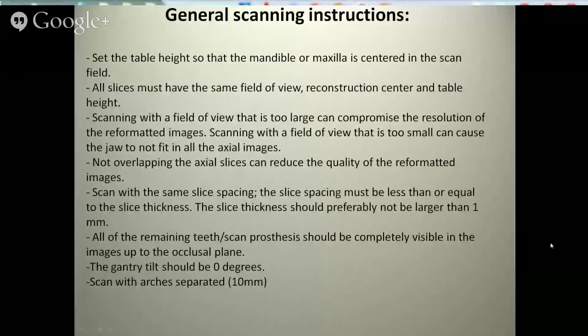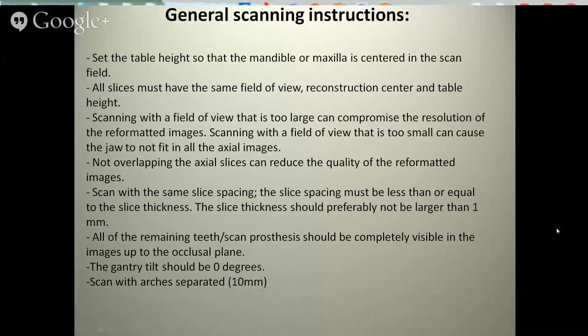Common to all machines is that the table height should be set so the mandible or maxilla is centered in the scan field, and that has to do with field of view. If that doesn't happen, the laboratory or your scan software company may call and say we didn't get the bottom of the mandible - it was cut off, and we don't know how much bone is down there. Things like that can cause you to have to rescan.